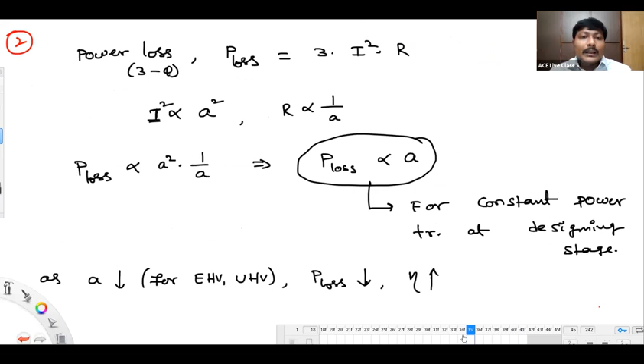See, any conductor carrying some current has some impedance, whether it is a distributor or feeder. Those are the names we have given. After all, if a conductor is carrying some current and has some impedance, definitely we have a voltage drop in it. There is no doubt about it. So we have a voltage drop in the feeder as well as in the distributor, both. But in the case of the feeder, even though you have a voltage drop, it is possible to maintain a good voltage profile by means of compensators.